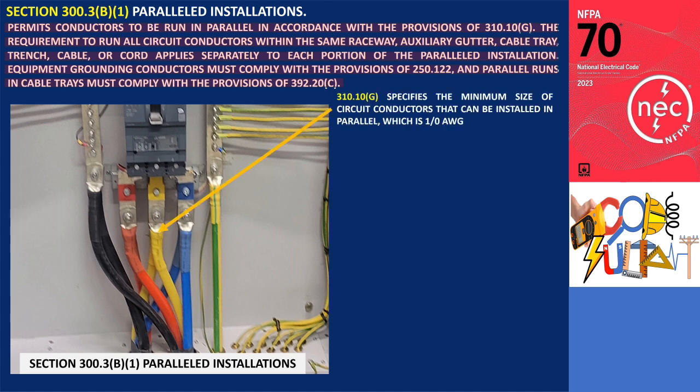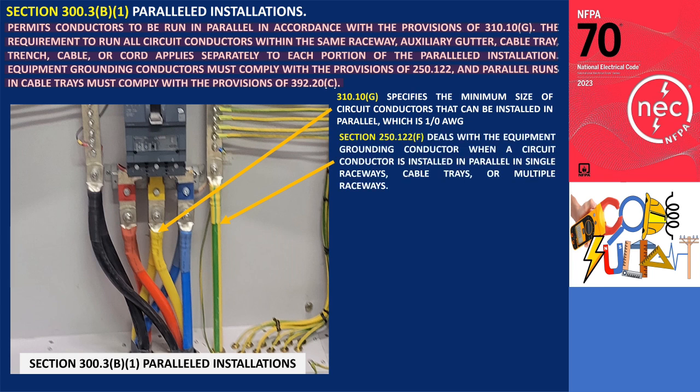Section 310.10 specifies the minimum size of circuit conductors that can be installed in parallel, which is 1-0 AWG. Section 250.122.f deals with the equipment grounding conductor when a circuit conductor is installed in parallel in single raceways, cable trays, or multiple raceways.